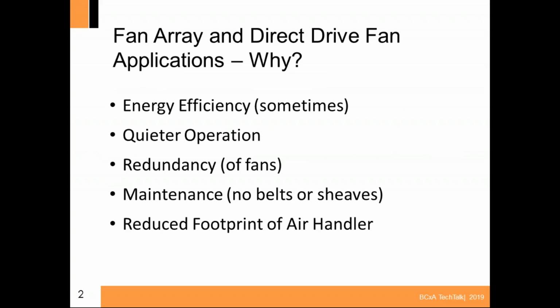Why would you use a fan array? Well, some people tell you that they're energy efficient, and that's not necessarily true. We'll get into that a little later in the slideshow and show you why it's sometimes not that efficient. Quieter operation, I would agree with that. They can be quieter than a very large fan. Redundancy seems like the big thing that all the owners want to go for. They want to see a 9-fan array where, if 2 of the fans fail, they still have some kind of air conditioning in there. I have an example later on in here.